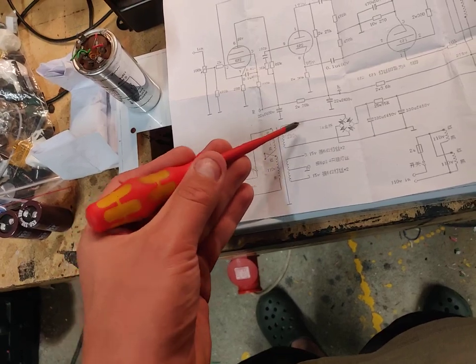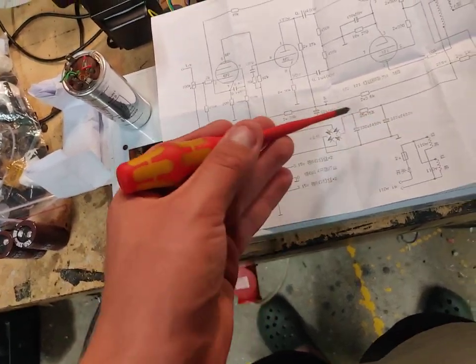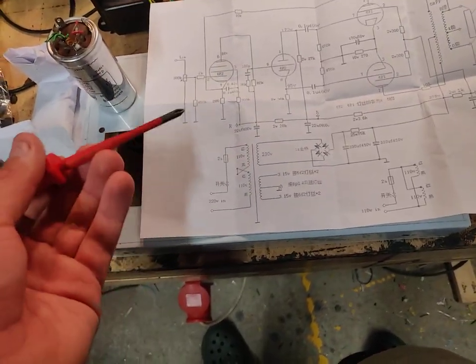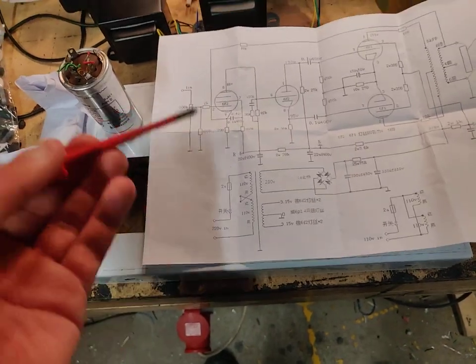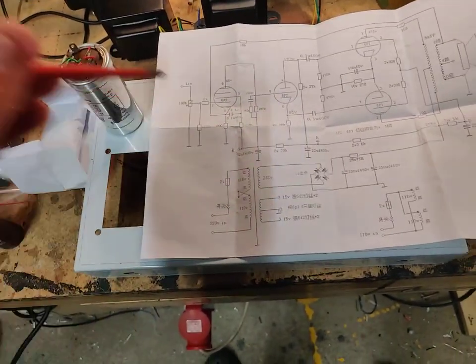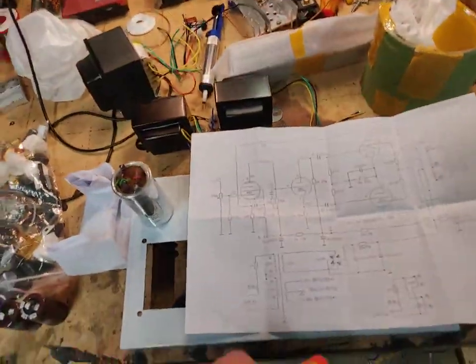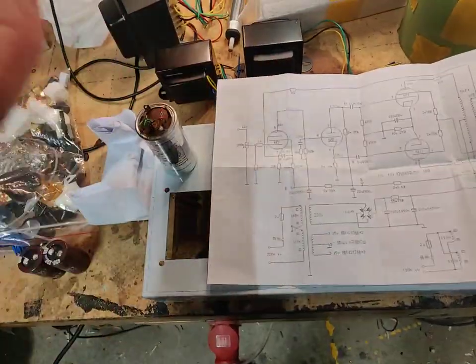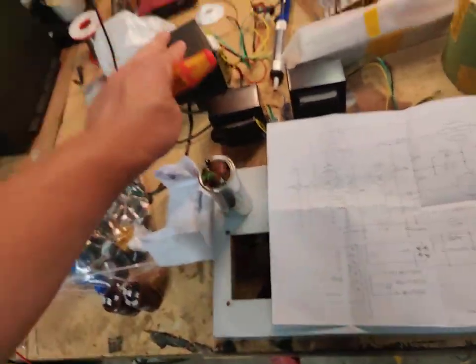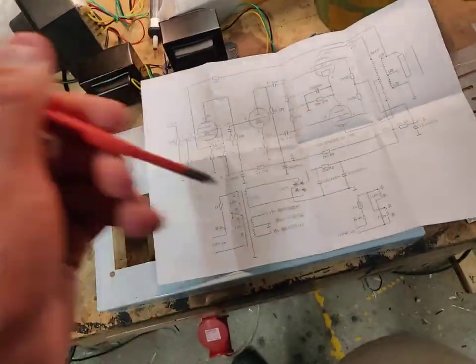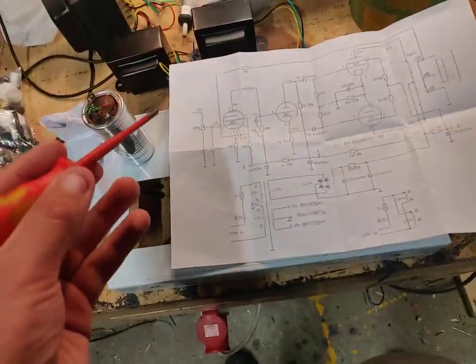Because it's going to be a large surge when you charge up the filter caps here. So slow blow, but I don't think 2 amps is necessary, it's too large, so just put a smaller one there, and you'll be able to save the transformer should something short out in the amp. Let's say your heater wire shorts out for whatever reason, it's going to pop that fuse and the transformer is going to survive. So you gotta be a little bit careful about stuff like that.